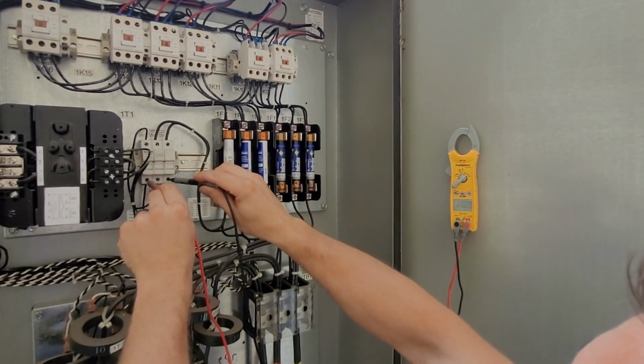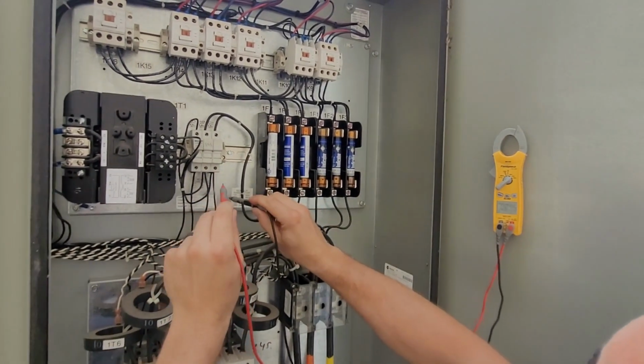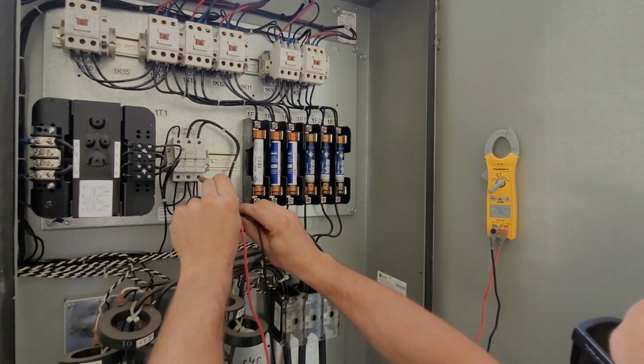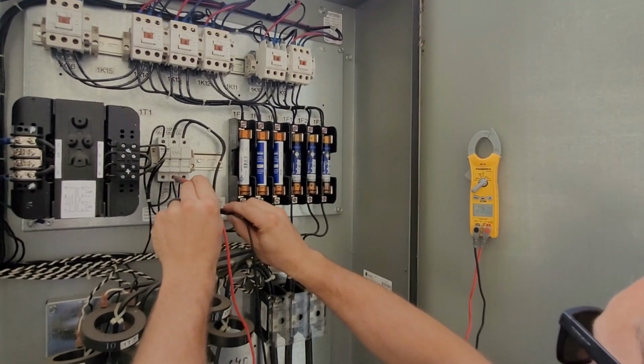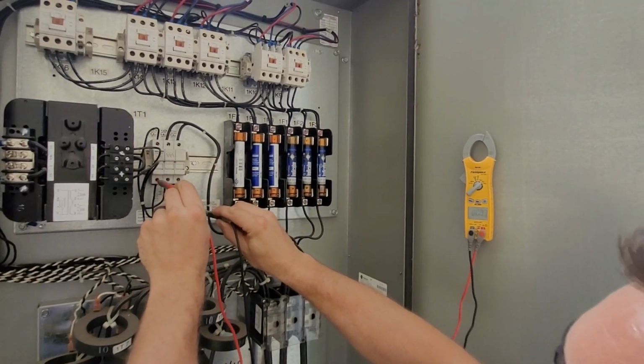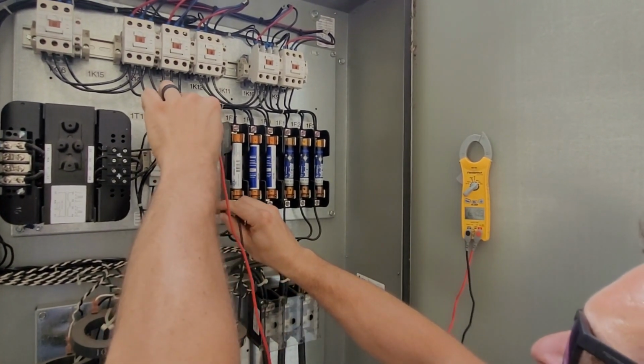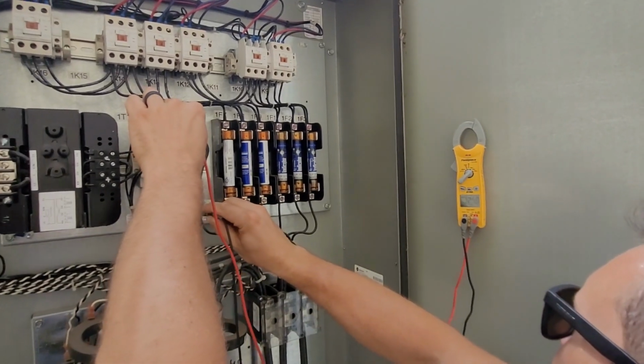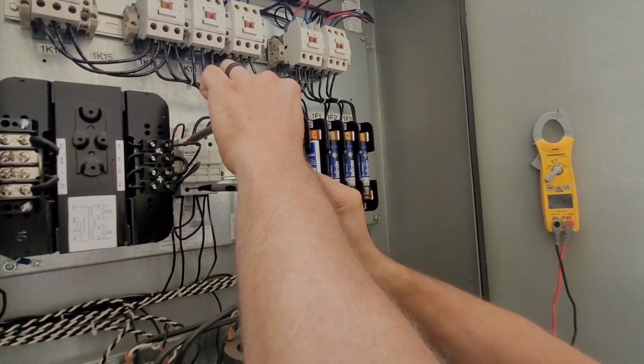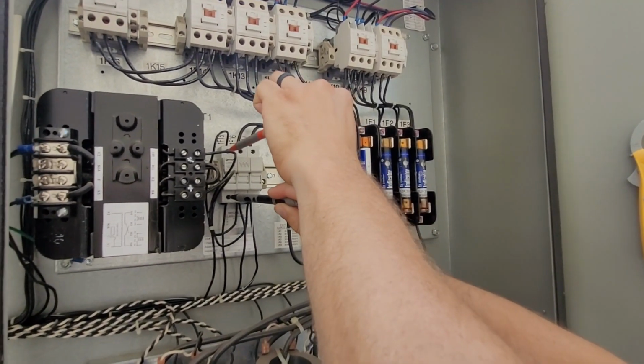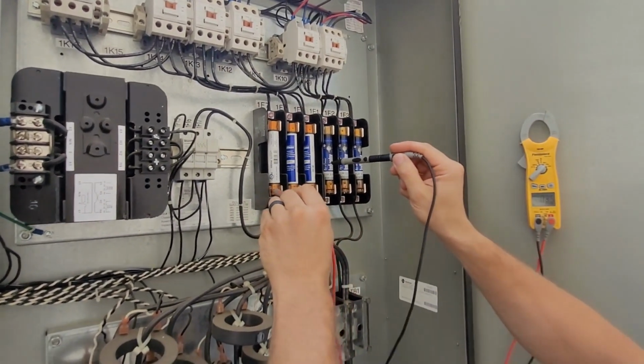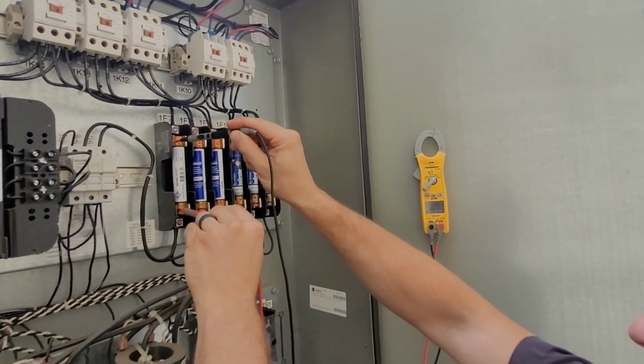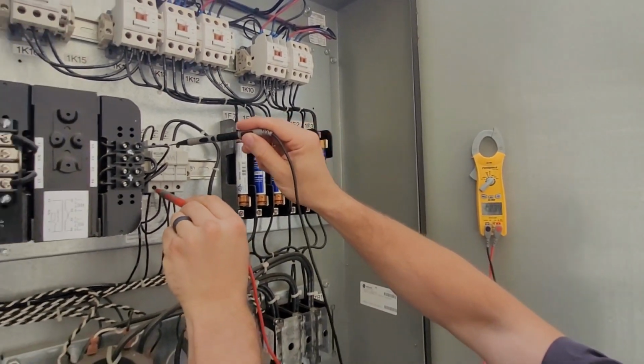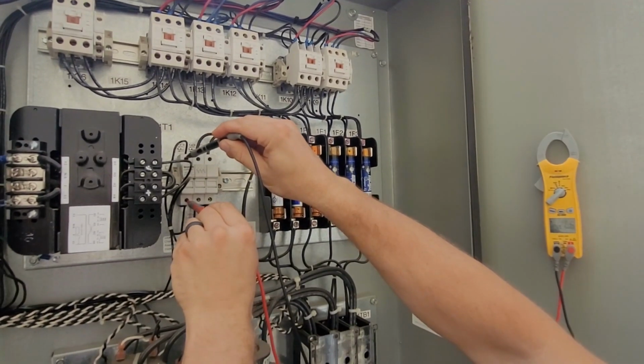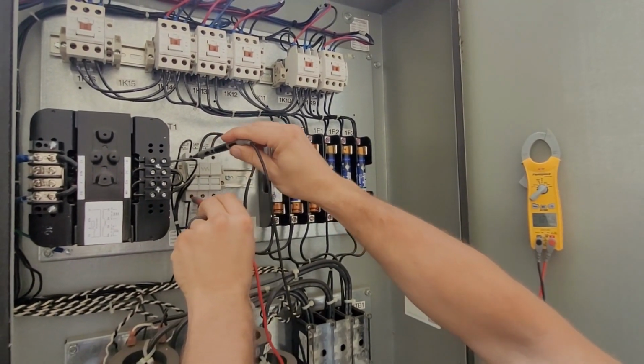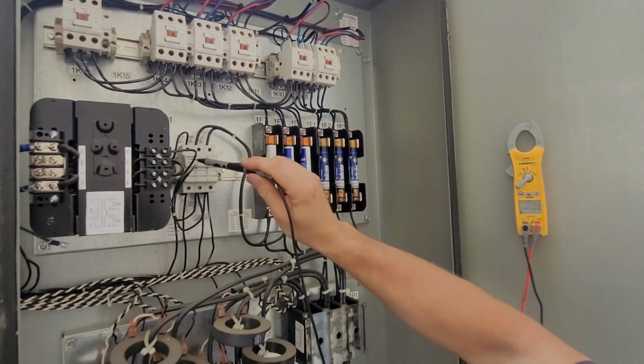So now I'm going to start checking things to ground. So 208, 208, nothing. All right, go up top on the fuse, 120. Go across the fuse, 120. If you're going across something, it should read 0 like this. Same leg, it's going to read 0, right? Well, if the fuse is blown, it's kind of like one leg to ground. So I'm looking at this fuse as being the culprit.